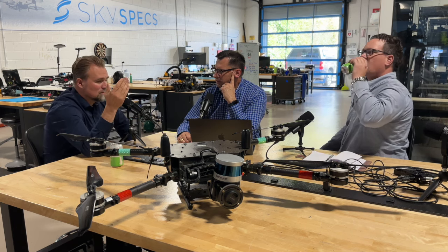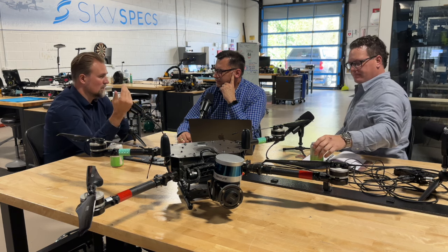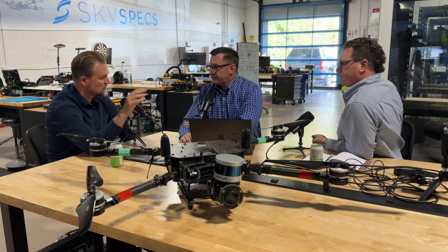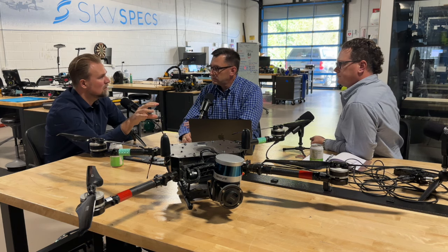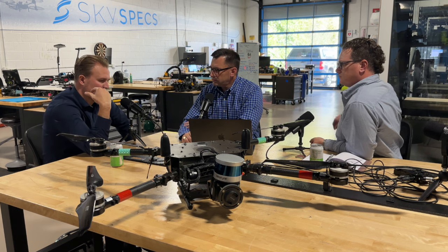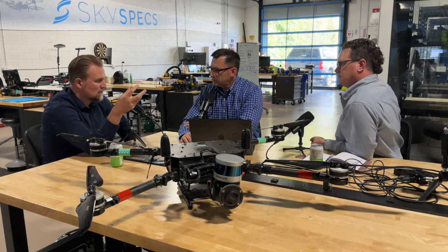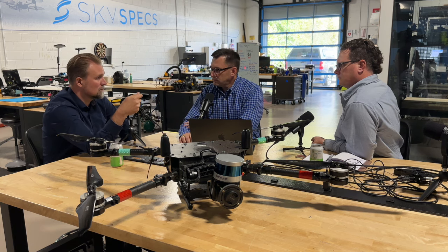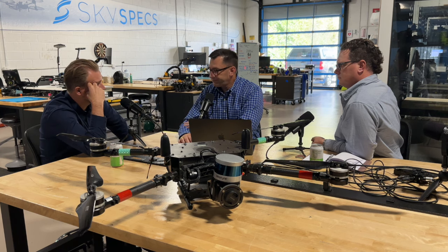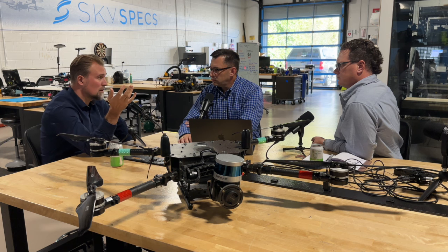So let's say that you detect damage on a main bearing, right? We're not predicting that something might happen. We detect something that is happening right now, like damage that's ongoing and that will last a certain amount of time. The diagnostic piece of that is saying it's an inner ring fault, or an outer ring fault, or a bearing spalling issue or something like that. You can diagnose it down to a really specific level, but regardless of what it is, you're going to have to exchange that main bearing at some point.